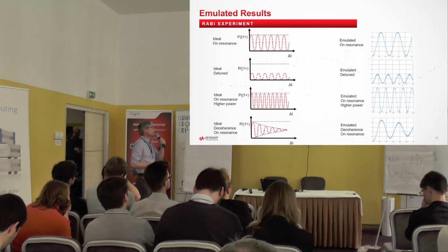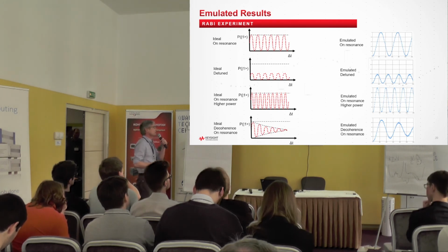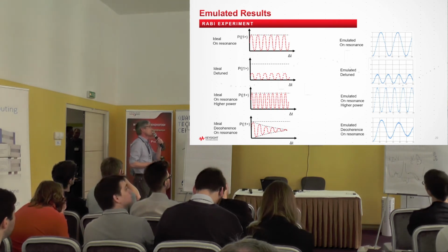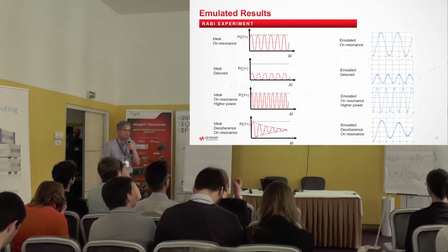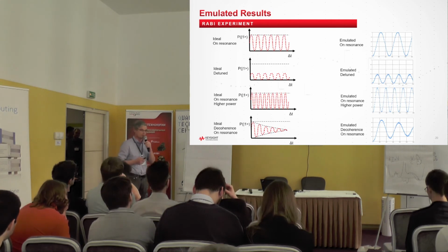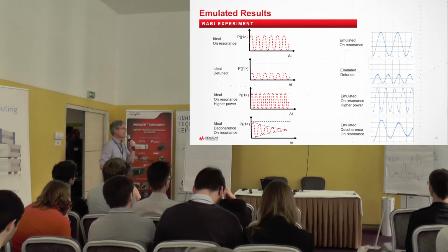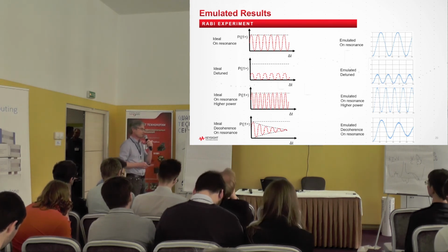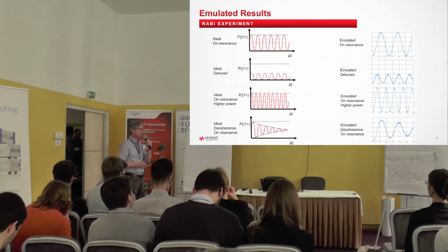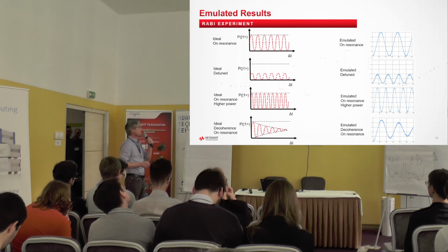So these are the results obtained from the emulator using the scripts that we are providing. Basically we are providing to our customers example control scripts for making all these kinds of measurements, like Ramsey, spin echo and randomized benchmarking, so many kinds of experiments. If you run them on an emulator, you will get results that are really similar to what you have in real life.